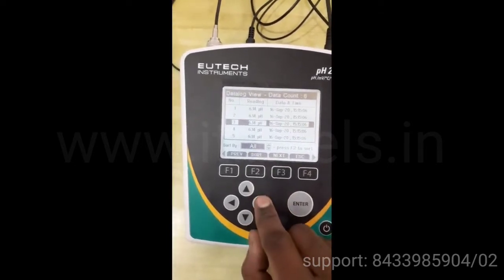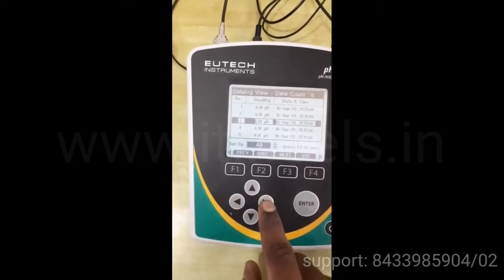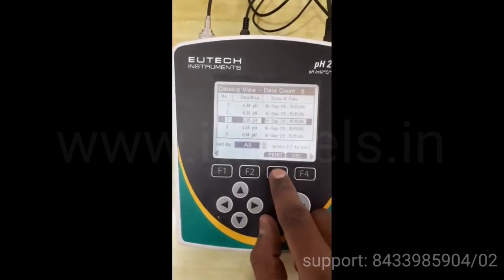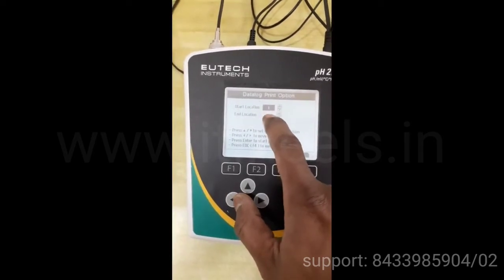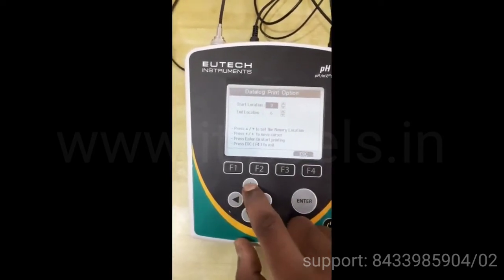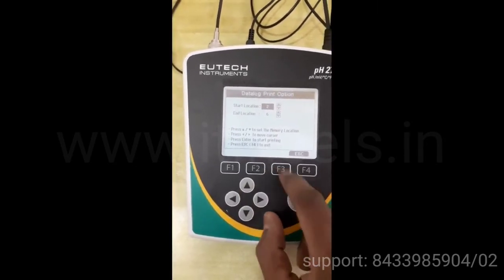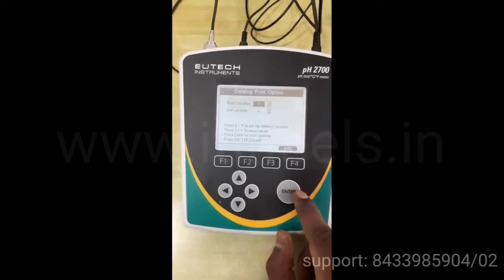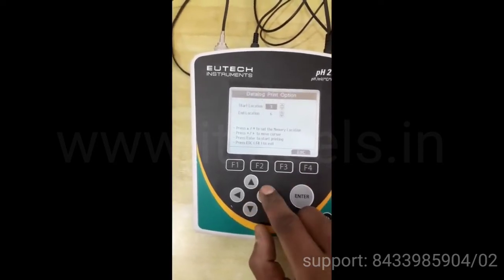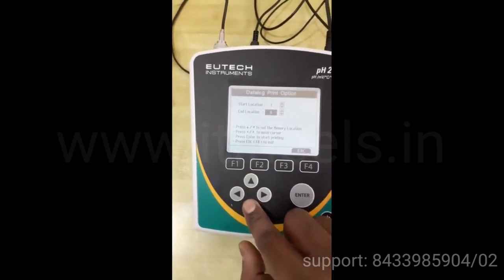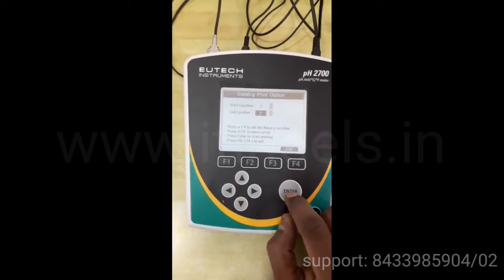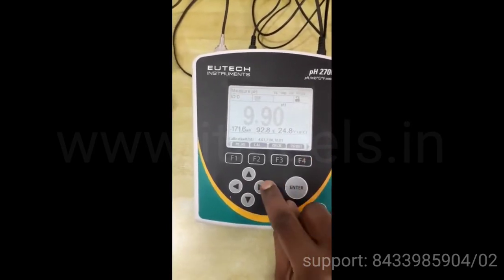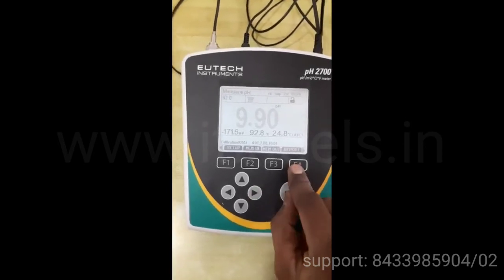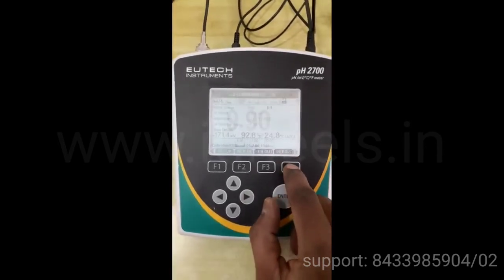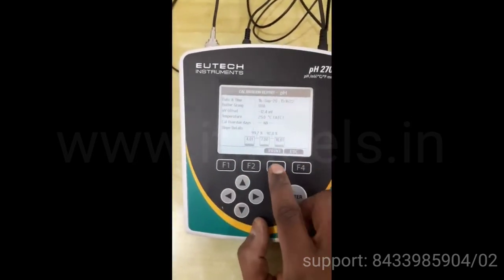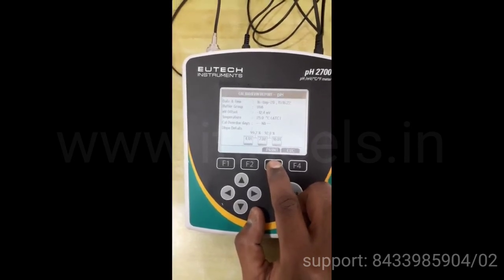So you can take a printout of these readings also by pressing any of these keys, next, and the print option. Now you have to press this button and select the location point, start and end point, from 2, then press. So from 2 to 6 it will get printed. You can change the location from here and press enter to take the printout. This is the report. To take the printout of the report, you have to press this button and you can take a printout of the calibration report which gets stored. By pressing this, you will get the printout.